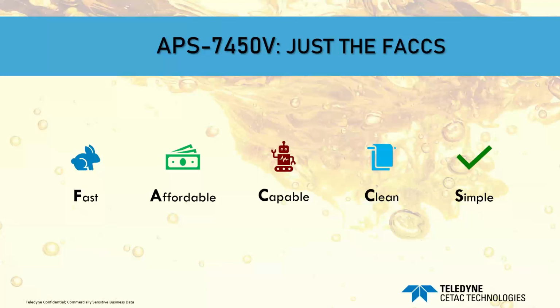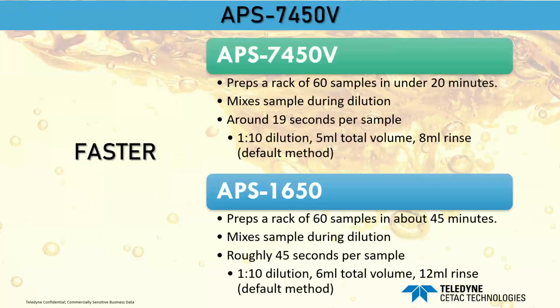But I'll explain, starting with fast. I started out, I said it was a workhorse. Probably what I should have said is this is a racehorse, because the APS 7450V is truly fast. The 7450V is the successor to our APS 1650, and if you're familiar with it, the APS 1650 could dilute a rack of 60 samples to 1 to 10 in about 45 minutes. Now, that wasn't bad, but we knew we could do better. The 7450V shatters that time by preparing 60 samples to 1 to 10 in only 20 minutes. So we're talking less than half the time.